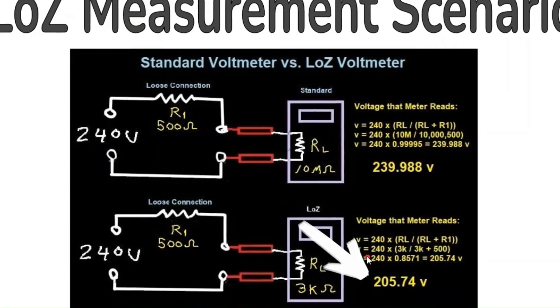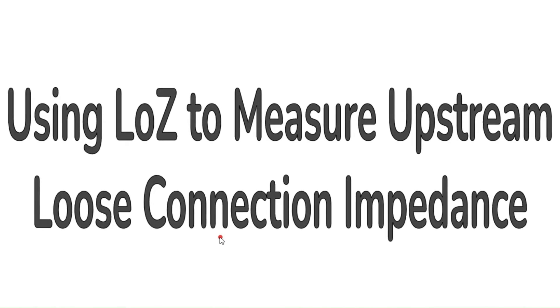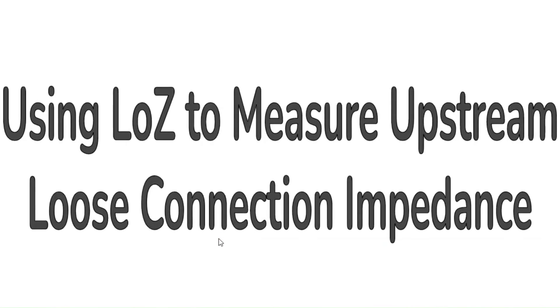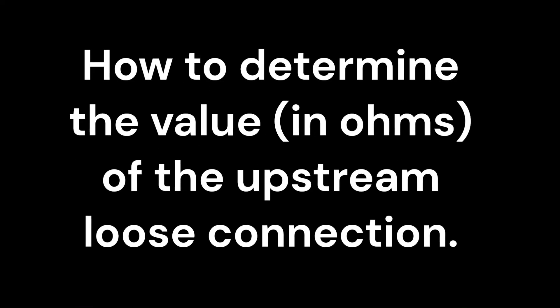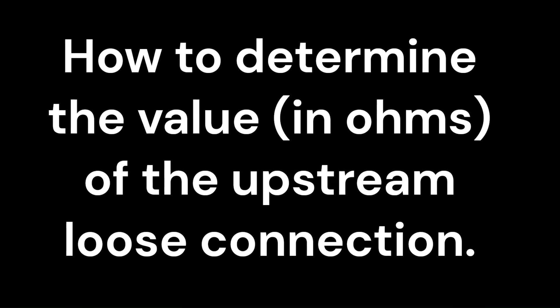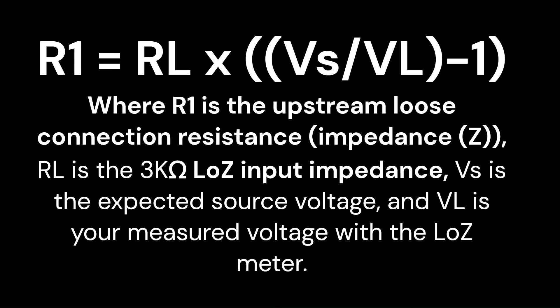Details on how this works can be found in the link in the description of this video. You can even use the low Z meter to tell you the value in ohms of the upstream loose connection. In our example, the upstream loose connection was 500 ohms. There is a formula that you can use to determine that value if you are in the field and would like to give a follow-up electrician details about the voltage source failure.